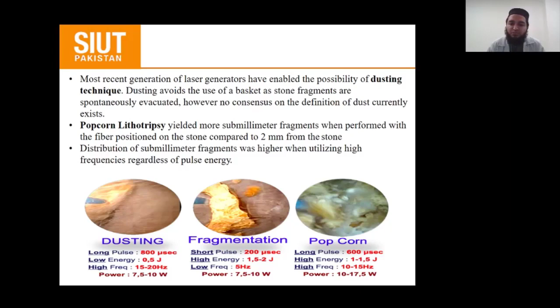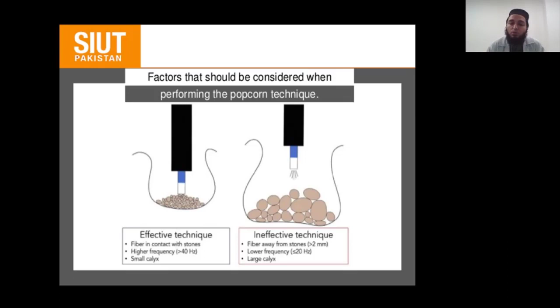So the favorable factors for popcorn lithotripsy, or the effective technique, are that the fiber should be placed over the stone, at the stone, and the frequency should be higher, greater than 40 hertz. For the popcorn technique, a short calyx is preferred. For an ineffective technique, there is a large calyx. If the frequency is less than 20 hertz, it will be ineffective. And if the probe is kept 2 millimeters or more away from the stone, then the popcorn technique will be ineffective.